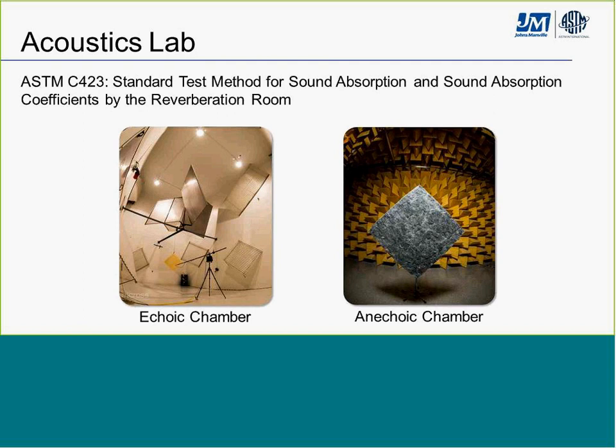Another area of expertise is acoustics, where we use a reverberation room to calculate sound absorption coefficients. The test method tells us microphone placement, how many diffusers are needed, how often microphones should be calibrated, and how to calculate and present results. We also have an anechoic chamber, and because there are specifications around that, you can take results from our lab, run the same test in another lab, and get consistent results — ensuring the industry has the best information to work with.